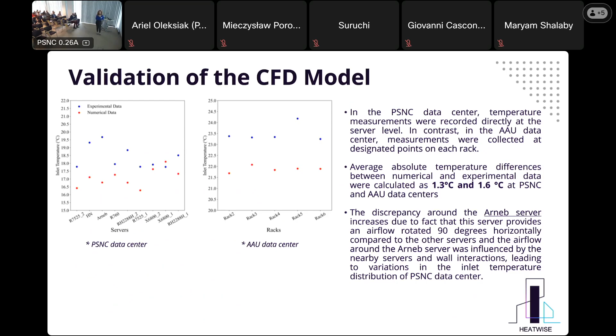In the PSNC data center, temperature measurements were recorded directly at the server level, because we did server level modeling. In contrast, in the Aalborg data center, measurements were collected at designated points on each rack. So they collected the temperatures rack by rack, and we did rack level modeling. Average absolute temperature differences between numerical and experimental data were calculated as 1.3 Celsius and 1.6 Celsius at the PSNC and Aalborg data centers, respectively. And the discrepancy around the Arneb server, as I stated before, is because of the horizontal location of the server.